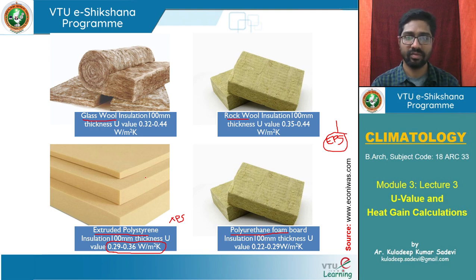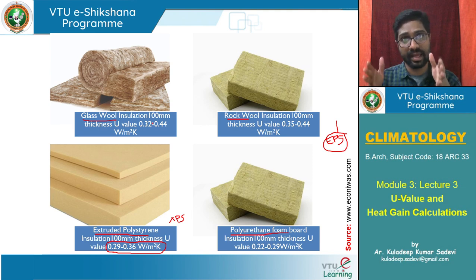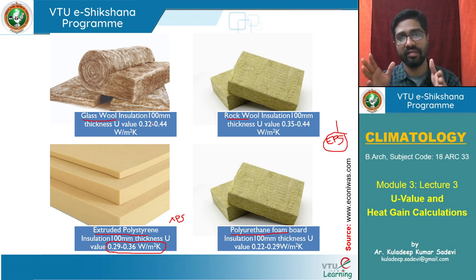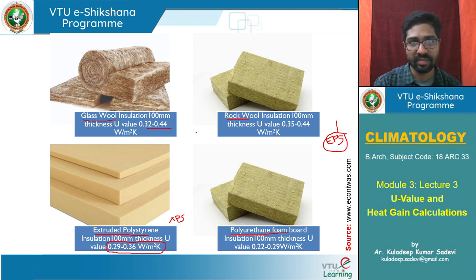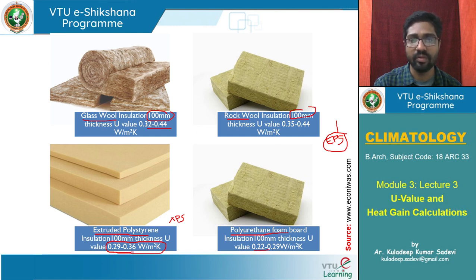These are four different insulating materials. Comparing U-values: a 300 mm thick AAC wall has roughly 0.5 W/m²·K, but all four insulating materials — at only 100 mm thickness — have much lesser values: 0.29, 0.32, 0.35, and 0.22 W/m²·K respectively.